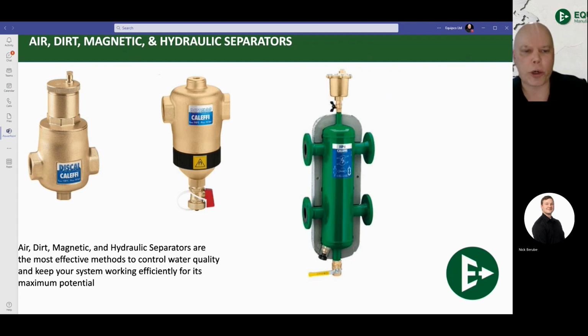So your next piece on the line, that's your dirt separators. Almost all dirt separators now are both dirt and magnetic, where they can catch things like, first of all, your ferrous materials coming off inside of your system, and also the iron in your water if you filled it with just tap water, but then you treated it, so it's going to be okay. And with the dirt separators, such as this one here, you're also going to catch the non-metal or non-magnetic or non-ferrous material in the system as well. Now, there are some dirt separators out there that are magnetic only. They will never, ever catch things like Teflon tape, solder balls, flux, plastic shavings from PEX tubing and stuff like that. It won't catch them. So if you ask me, what's the point of them? I have honestly no idea.